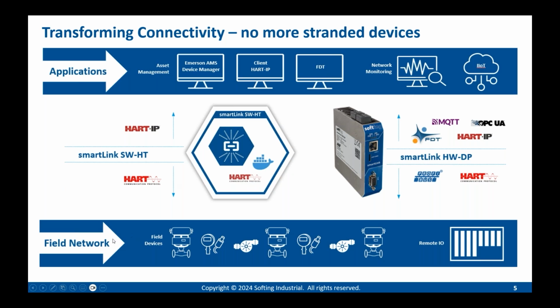You can see that these kinds of field devices, pressure sensors, transmitters, valves, etc., are connected to the remote IO. These remote IOs might be speaking Ethernet or Profinet, and through the SmartLink software version, you can send it via HART IP to AMS Emerson AMS Device Manager, or to a HART IP client, or to any kind of FDT application. It's just a software that runs on your computer, and you don't need any additional hardware for that.